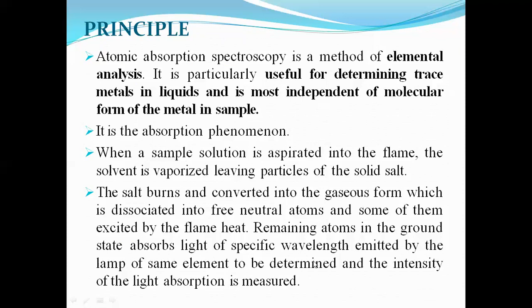The instrumental part of atomic absorption spectroscopy consists of a radiation source, chopper, atomizer, monochromator, detector, and readout device. This is the block diagram of atomic absorption spectroscopy. The first part is the hollow cathode lamp. This is the radiation source, which passes radiation of different wavelengths, and this is the flame in which our sample is introduced from the bottom side. Here it is the analyte sample in a beaker. It is passed through a nebulizer with the fuel-air mixture into the flame, where it vaporizes and atomizes. In some instruments a chopper is used to convert the steady light into a pulsating light.